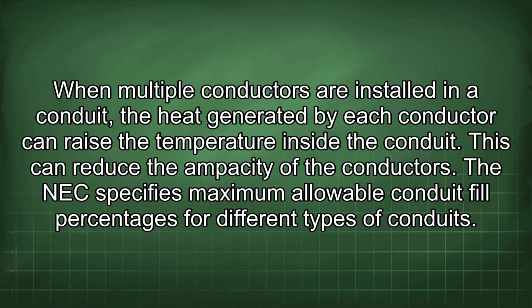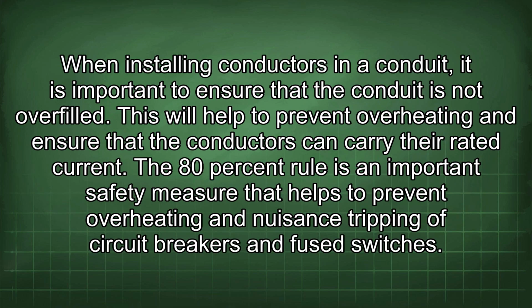When multiple conductors are installed in a conduit, the heat generated by each conductor can raise the temperature inside the conduit. This can reduce the ampacity of the conductors. The NEC specifies maximum allowable conduit fill percentages for different types of conduits. When installing conductors in the conduit, it is important to ensure that the conduit is not overfilled. This will help to prevent overheating and ensure that the conductors can carry their rated current.